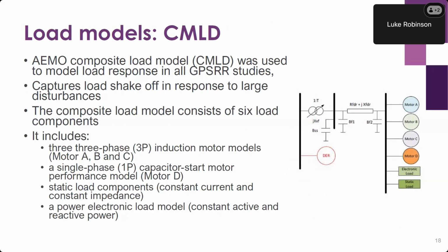I'll just go into a little bit more detail about the composite load model. This was used in our studies to model load response. The importance of this is that it captures load shakeoff in response to large disturbances. The composite load model consists of 6 load components, and these include three-phase induction motors, A, B, and C, that have varying inertia, impedance, and torque properties. One single-phase motor D, which is a specially developed performance model based on lab tests representing refrigerator compressor motors, which are prone to stalling behavior, though this component's believed to be small in Australia.